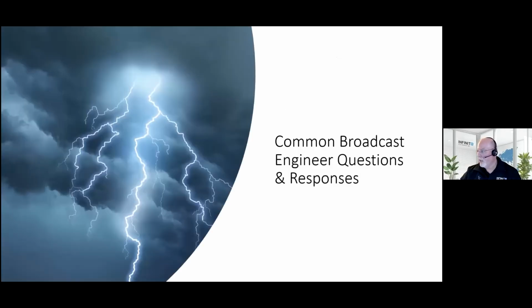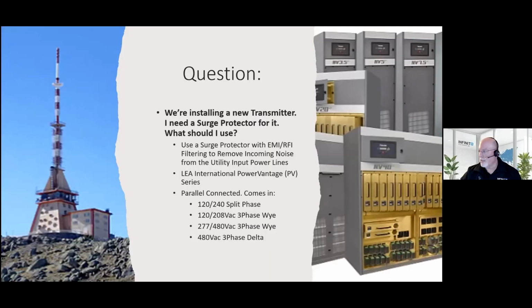Is that it for that? Yeah, okay. So we're getting down to the end of this presentation here, and what we have are some questions that I'm asked regularly by broadcast engineers. One of the most often asked questions is, we're putting in a new transmitter site, and what surge arrestor do I need? So we're going to ask you about voltage, what voltage configuration you need. Would you like filtering or not filtering? And whatever your other requirements are. But for broadcasts, having a filter is great. Like I say, it eliminates some noise from the incoming utility. And so there you go.